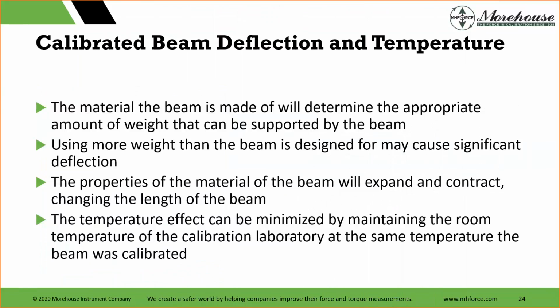So, calibration beam, deflection, and temperature. I sat through this long conversation at the National Institute of Standards and Technology. The person gave an excellent presentation on torque and torque error. And at the end of the day, I was like, wow. I talked to people. I said, wow, that was really a great presentation. At the end of the day, one person in the class said, you know that guy, his lab isn't even controlled to within plus or minus 7 degrees C, which just completely deflated almost everything that the person said, because that's huge error. As that temperature changes, the length changes.